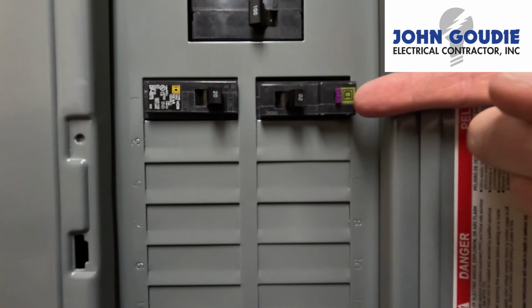The majority of houses in the United States, this is what they have in their panel. But a few years ago, the industry came out with what's called an arc fault breaker, which is what we have here on the right. This one is a step up. It's kind of the Mac Daddy of circuit breakers. It has what's called circuit monitoring built into it. What it's monitoring is any arc that you have within this electrical circuit. It's not only monitoring arcs within your electrical circuit that an electrician would install, but it's also going to be monitoring anything you plug into that circuit.